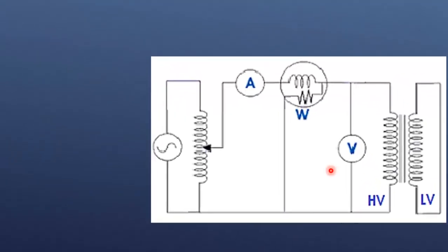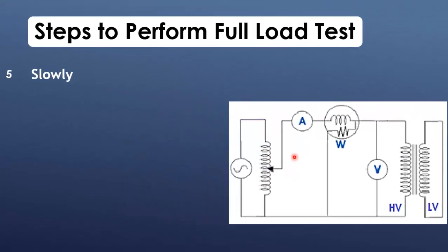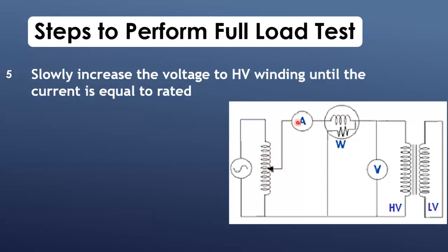Now after connection, let's perform the test. Since the low-voltage winding is short-circuited, the transformer will draw a large current initially, and the voltage applied to the high-voltage winding must be gradually increased to avoid overloading the transformer. Slowly increase the voltage until the current on the high-voltage side reaches its full-load current.